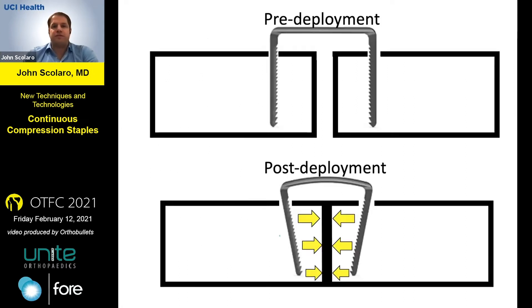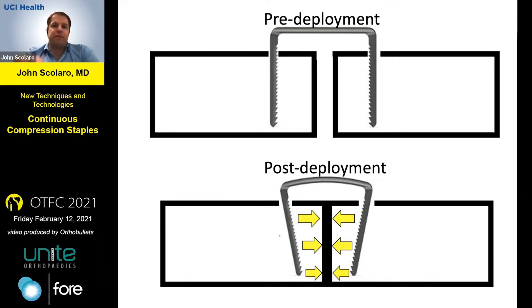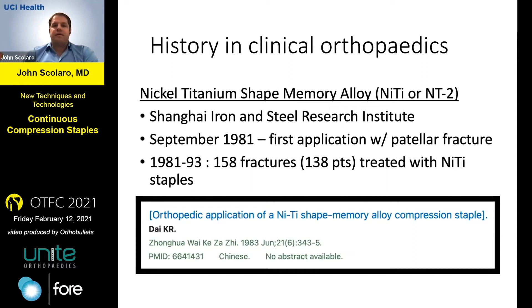If you've never seen these, here's the general gist of how they're used. You have two pre-drilled pilot holes placed bicortically across a small bone. There's a handle that spreads the two tines or ends of the staple apart. The staple is placed into the bone, and once the mechanism that opens the tines is removed, it deploys and generates continuous compression across the end of the staple.